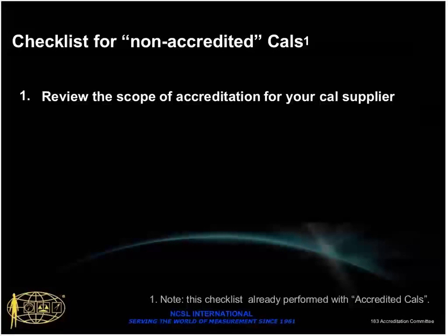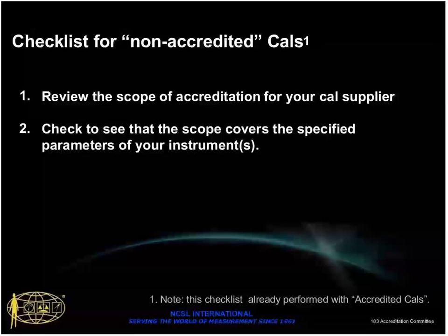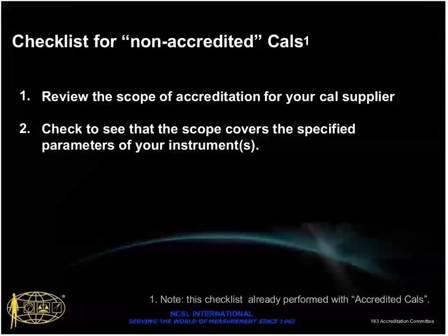So finally, I'd like to offer a little checklist of points that Trevor and I want to make on this first portion of accreditation. We're going to be talking about specific requirements for when you ask for the accreditation symbol on the certificate in a moment, and Trevor's going to take that over. But just to close out this portion, on what you should be aware of even when you don't ask for the accreditation body symbol, you should always, always review the scope of accreditation for the calibration supplier. Now, if you're not used to doing this, it may be a little tricky, but you can ask an Agilent representative for help, and we will try to show you how to do that if it's not obvious. But what you really want to do is make sure that the schedule of accreditation is going to cover the parameters that relate to your instrument.